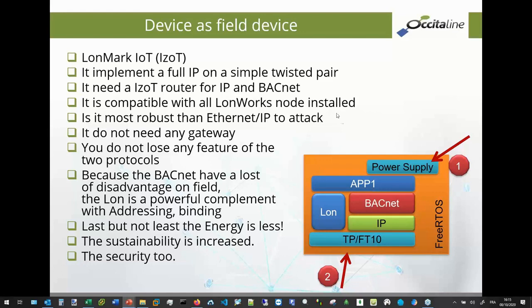For installing or managing these devices, in fact, we need a specific router, a standard router, because it's standardized, it's the IzoT router. And this router is a LON router supporting IP routing and BACnet routing, because you have an IP stack and a BACnet stack. If you have a Modbus stack just behind, in fact, we need to implement the Modbus access.